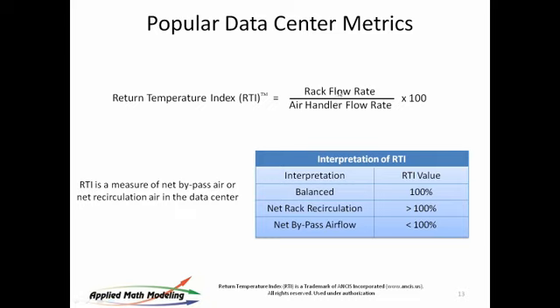And what you see here is that if the air handler, this is either CRAC or CRAH, however you want to look at it, if the cooling air flow rate is greater than the rack flow rate, it's going to drive this number down. If these are identical, if these are even, you're going to get 100%. If you don't have enough airflow here, this number will go positive. It'll go over 100%. So you see that it's balanced at 100%. If it's greater than 100%, you've got rack recirculation because you don't have enough air to supply the racks, and it will just wrap right around and go back in. They'll be breathing their own exhaust effectively. And if it's less than 100%, it'll be going right by the rack and back to the cooling system and cooling it off. So this is the first one that we look at, RTI.